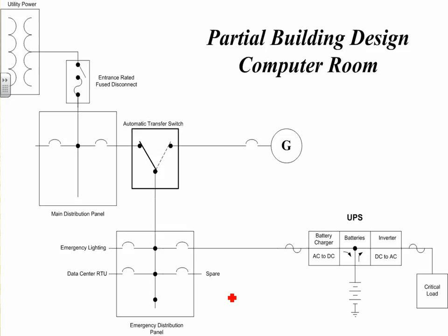If you have an emergency auto transfer switch, I always say it's nicer to have a bypass, so you can take it out, since all your electronics can fail at one time. But you don't have to. By code, you don't have to have a bypass. They get bigger with a bypass, yeah. Then you go by the basic minimum, which is a transfer switch that if it fails, it fails.